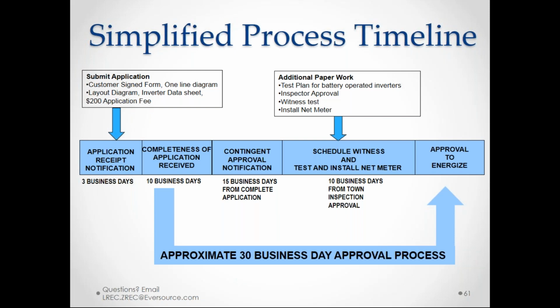We typically issue a contingent approval email, sometimes the very same day we begin the review process, or at least determine if it has failed the screen and requires further review, such as upgrades or adjustments to the inverter. We're becoming more open-minded on smart inverter-based solutions where if a project fails due to things like secondary voltage rise, rather than instantly requiring a transformer or wire size upgrade, there may be smart solutions like inverter settings. This is all case-by-case, so please don't assume anything. Let us do the review first, and if it fails, we'll communicate possible remedies.